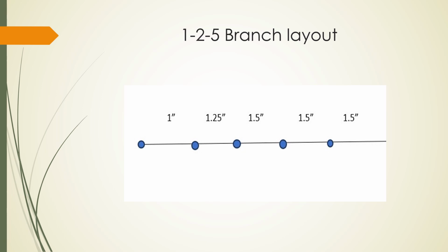I do want to comment just a bit on how we're establishing the adequacy of these sprinkler systems. When they were designed back in the day, they were designed with the concept of having a layout according to the scheduling, and then a water supply that had a pressure at the base, a flow and duration. The duration really depended on whether you were tied to a central station or not.